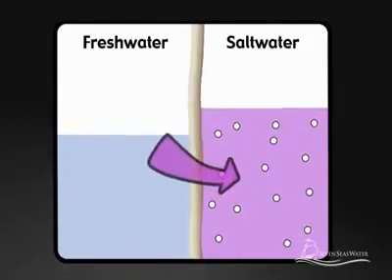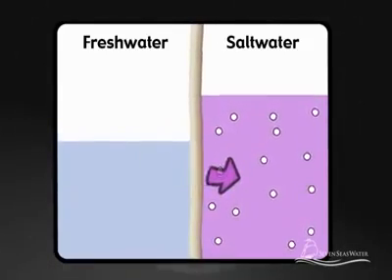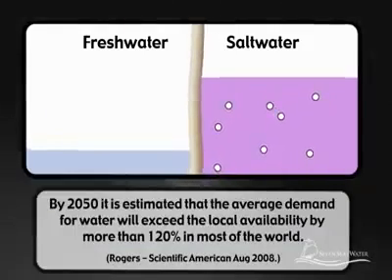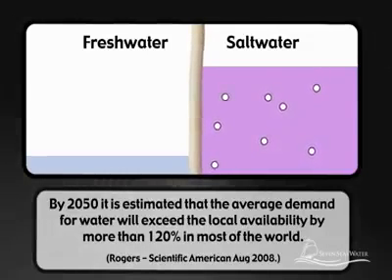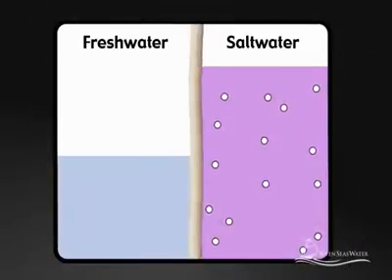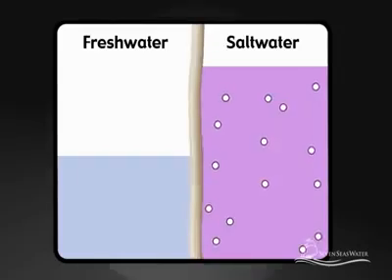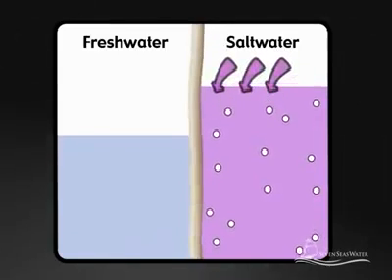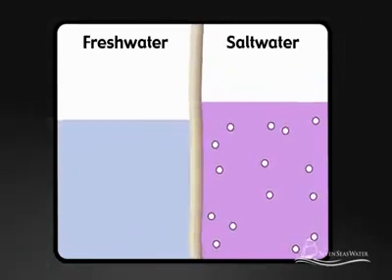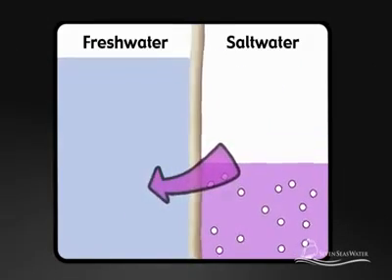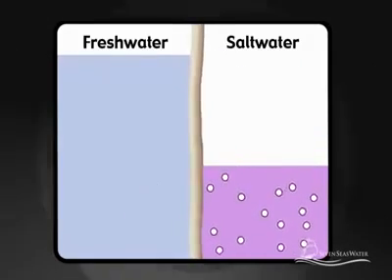In nature, the direction of flow through the membrane is from a less concentrated solution, such as freshwater, to a more concentrated solution, such as seawater, until equilibrium is reached. Reverse osmosis is when the opposite occurs. By pressurizing the concentrated solution — the seawater — we are able to force water molecules to pass from the salty seawater solution through the membrane to the freshwater.